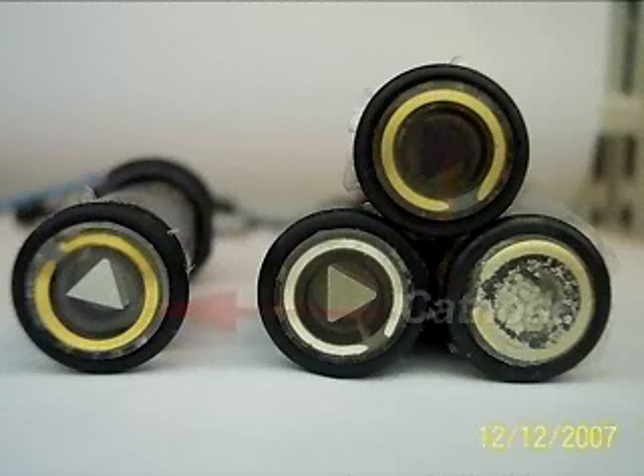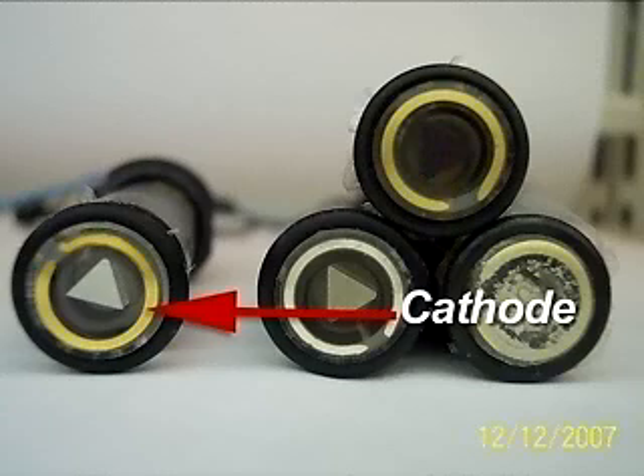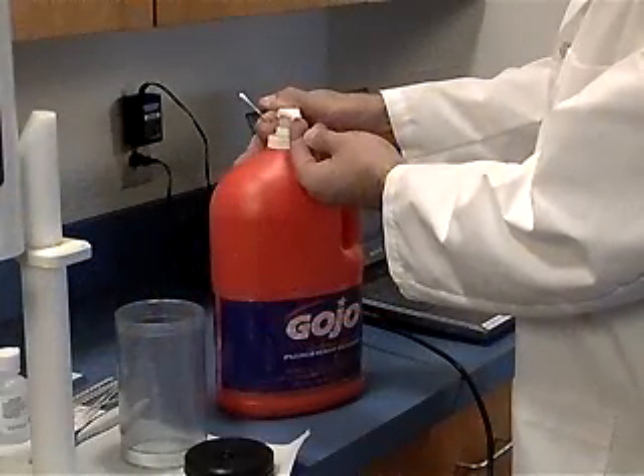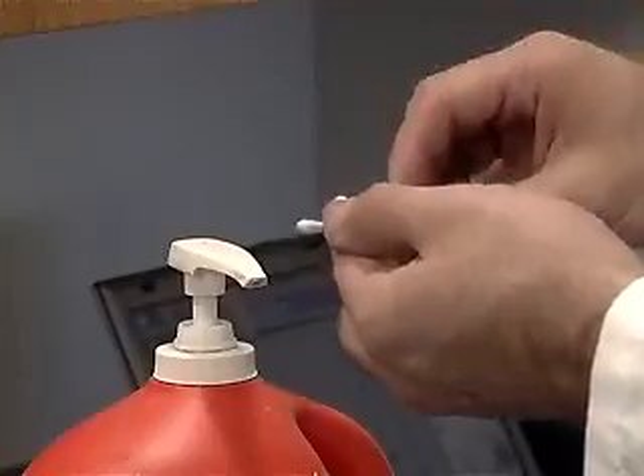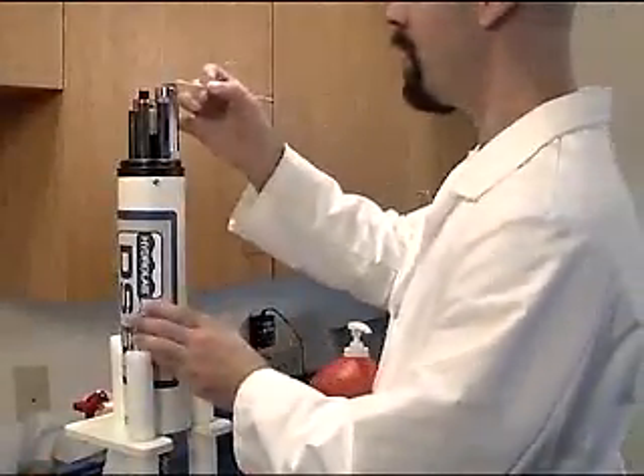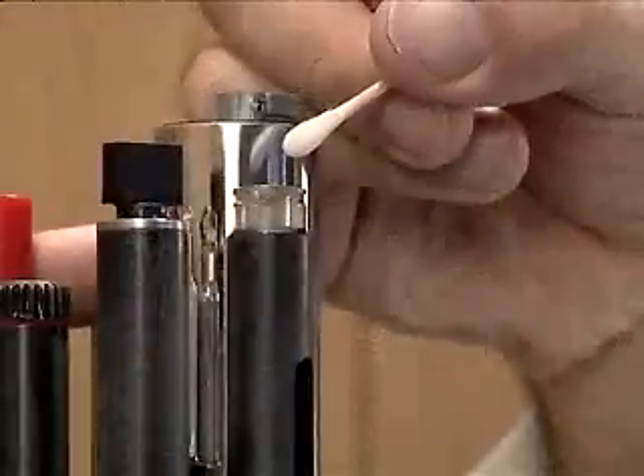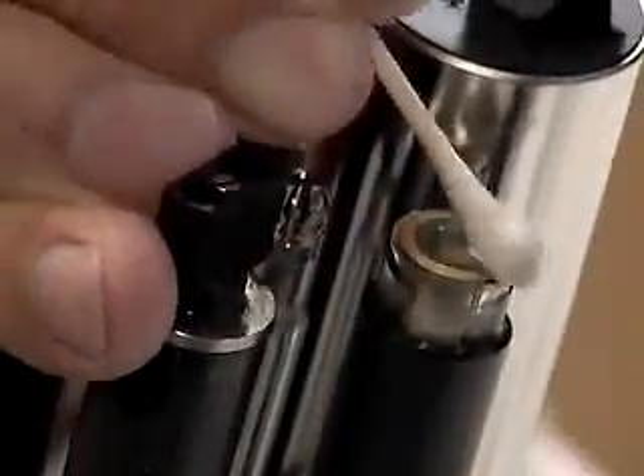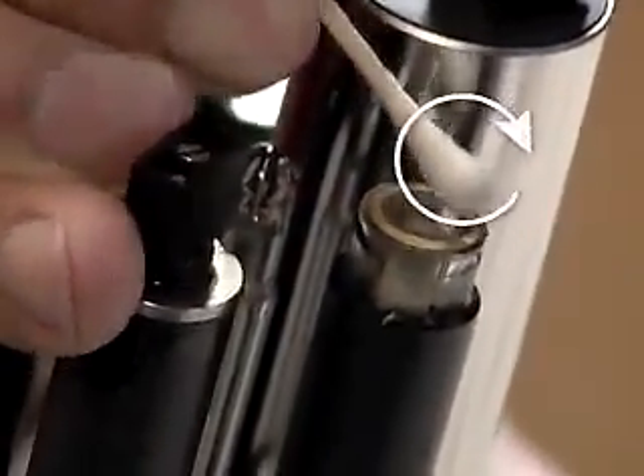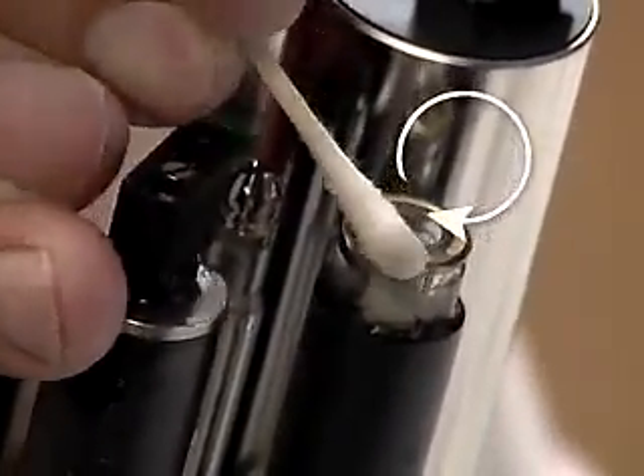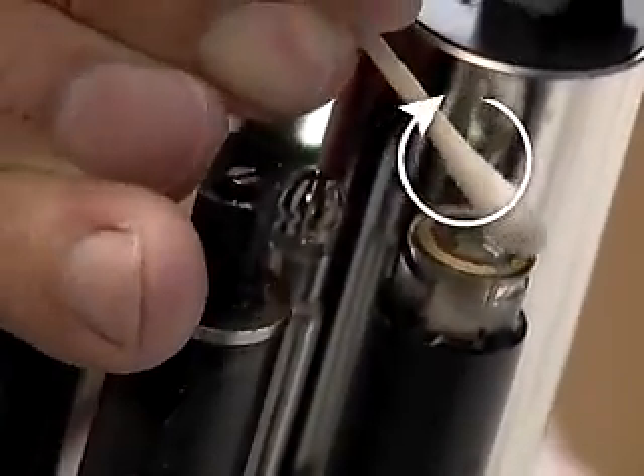The cathode is a gold ring around the top of the sensor. It should be a bright yellow. If it appears tarnished or dirty, it can be gently cleaned with a cotton swab and toothpaste, a mildly abrasive detergent, or hand cleaner with pumice. Rub the swab around the ring in a clockwise motion to prevent accidental damage to the sensor.